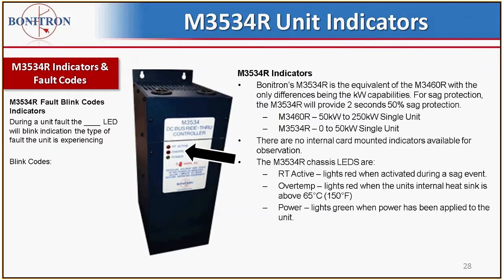For sag protection, the 3534R will provide 2 seconds, 50% sag protection as the 3460s do. The difference is the 3534s are a single wraparound chassis enclosed unit, and they will handle 0 to 50 kilowatts for a single unit. The 3460s start at 50 kilowatts and go to 250 kilowatts per single unit. Once again, there are no internal card-mounted indicators available for observation.